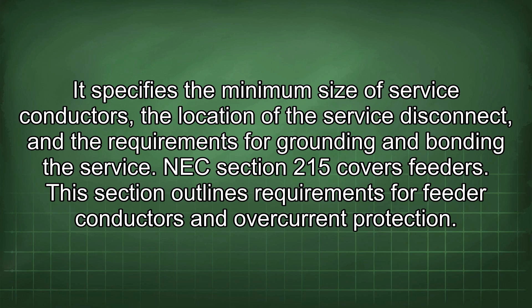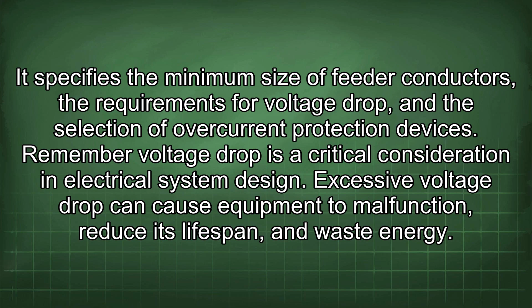Remember, voltage drop is a critical consideration in electrical system design. Excessive voltage drop can cause equipment to malfunction, reduce its lifespan, and waste energy. The NEC recommends limiting voltage drop to no more than 3% on feeders and 5% overall, including both feeders and branch circuits. Several factors contribute to voltage drop, including conductor size, conductor length, load current, and power factor.